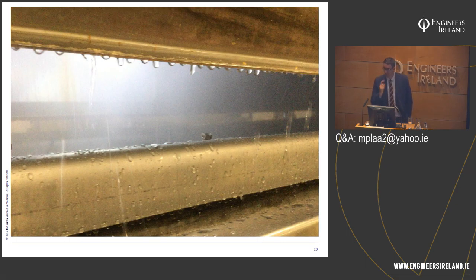Gary, what's the discharge time typically for travelling ovens? It depends if it's a high pressure system or a pump based system. Normally for a pump based system we'd ask for a 30-minute duration. For the stored pressure you're normally looking at a 10-minute supply.